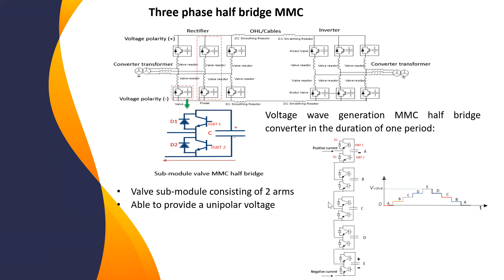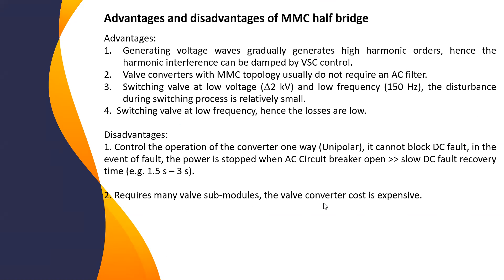The disadvantage here is that for half bridge, because we have only monopole, unipolar voltage, in case of any DC fault, the DC fault recovery will be long. Why? Because when we block the IGBT, the current still goes through the diode. And why do we need 1.5 seconds? This is because we need the circuit breaker to stop the power. This is the disadvantage of half bridge, meaning the fault recovery will be longer, depending on how fast the AC circuit breaker works. The other disadvantage is that we need more submodules because we build the power with discrete voltage. Every time we need a submodule, the increment is only 2 kV. So imagine if we have 500 kV, we have to switch more than 250 times.